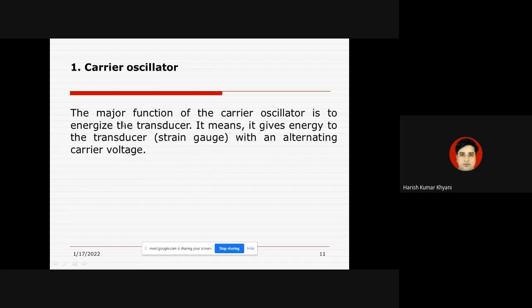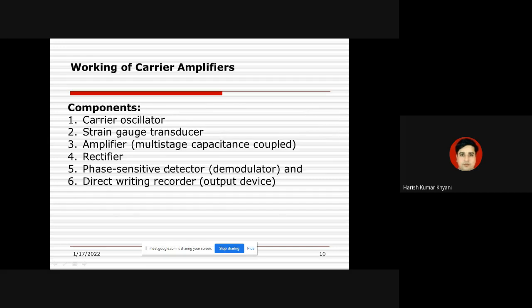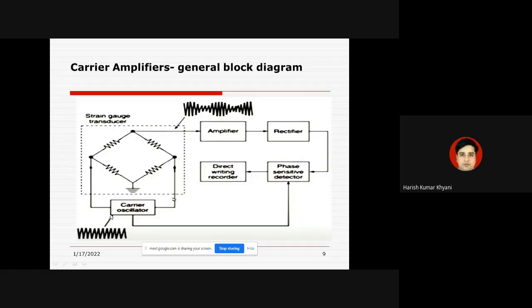The major function of the carrier oscillator is to energize the transducer — it provides supply to the transducer. We are using a strain gauge in this case, supplied with an alternating carrier voltage, which is the carrier signal. In the block diagram, the carrier oscillator generates this carrier signal, whose main function is to give supply to the strain gauge.